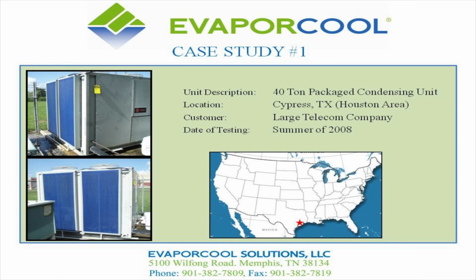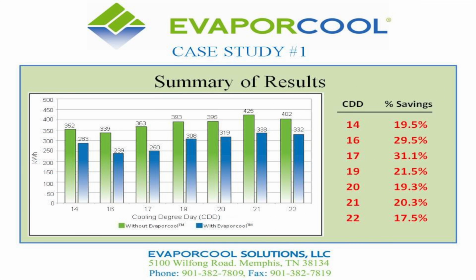So just to run through a couple examples, this is a 40-ton package unit in Houston. You can see, based on the cooling degree days, the amount of savings we were receiving. The bar chart shows the green bars without the Evaporcool system and the blue bars with the Evaporcool system. You can see the percentages of savings, but there's nothing under 17% savings on that unit, and it goes all the way up to 31%. So these are real savings. These are not something that we've manipulated in a spreadsheet.